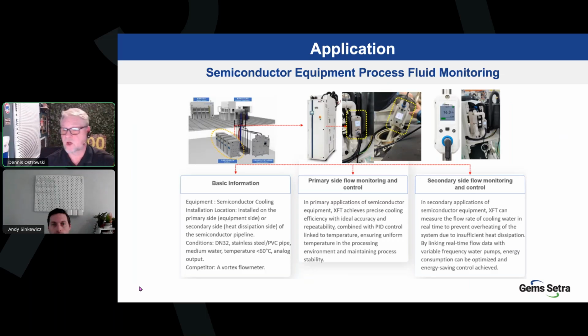This application, this is all real world application. You see the images here of the product actually in operation. It was installed both on the primary and secondary side. It had real-time flow data, and it was able to save them because they used variable frequency water pumps. And in monitoring in real time the flow rate, they were able to do energy saving optimization through this application. Next application.